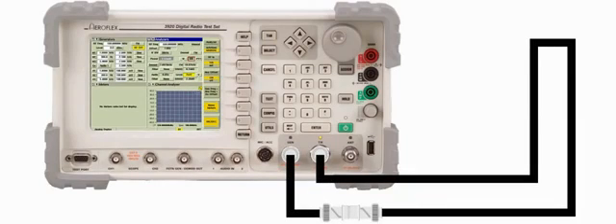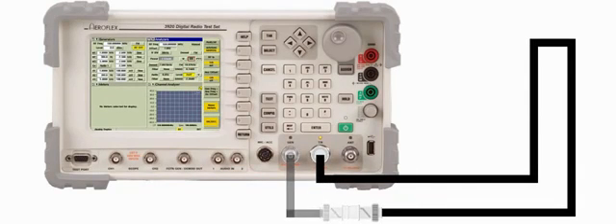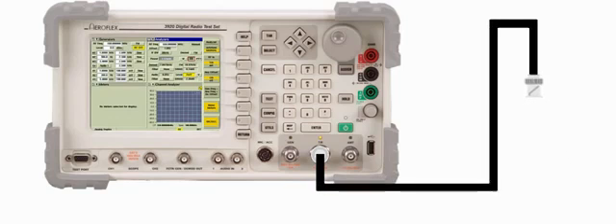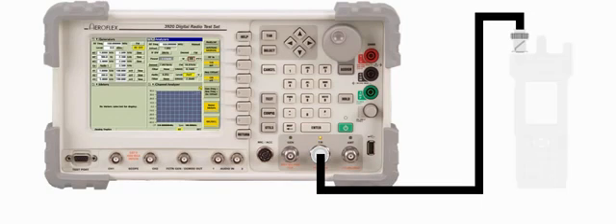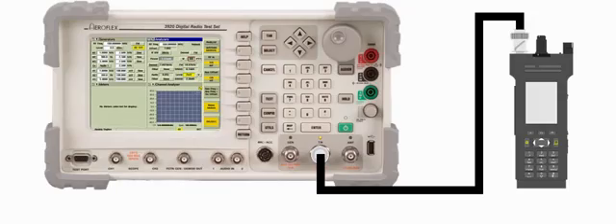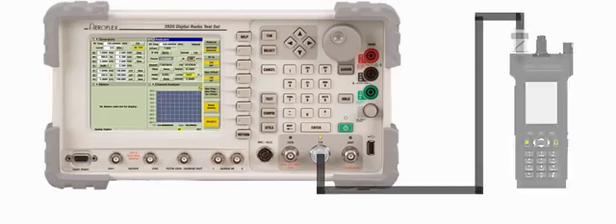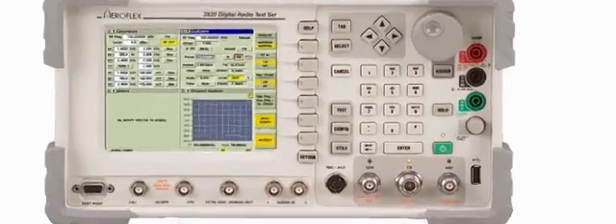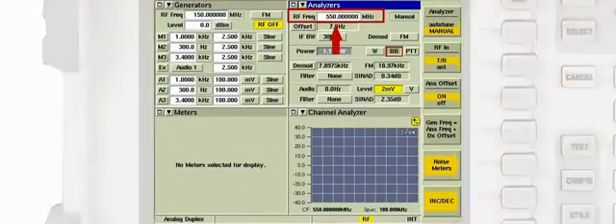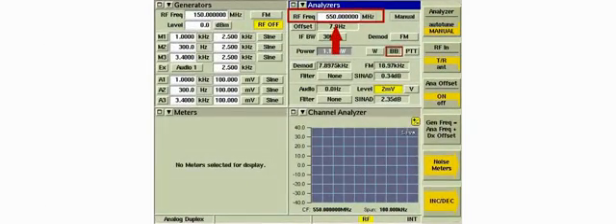We'll remove the reference cable and connect the radio to the TR port using the test cable. We'll enter the transmitter frequency of the radio into the RF frequency field of the analyzer's tile, then key the radio.